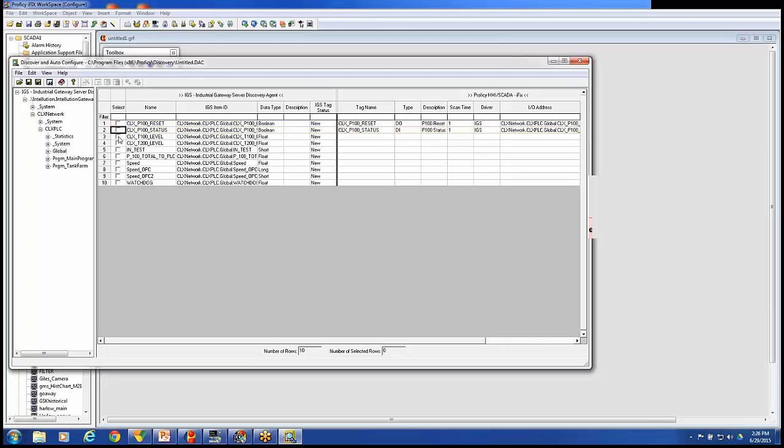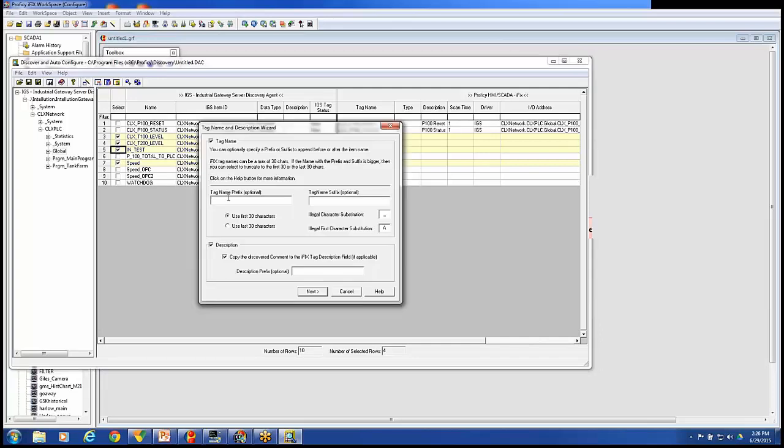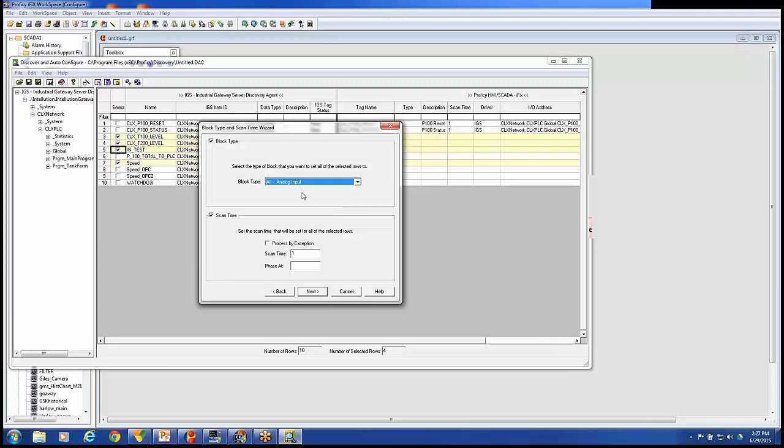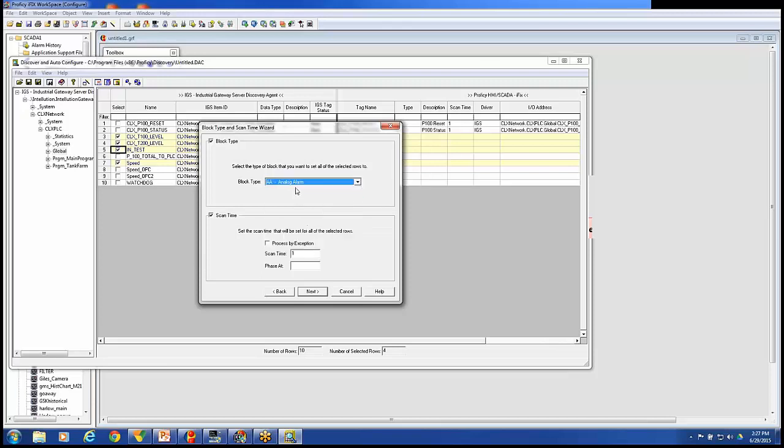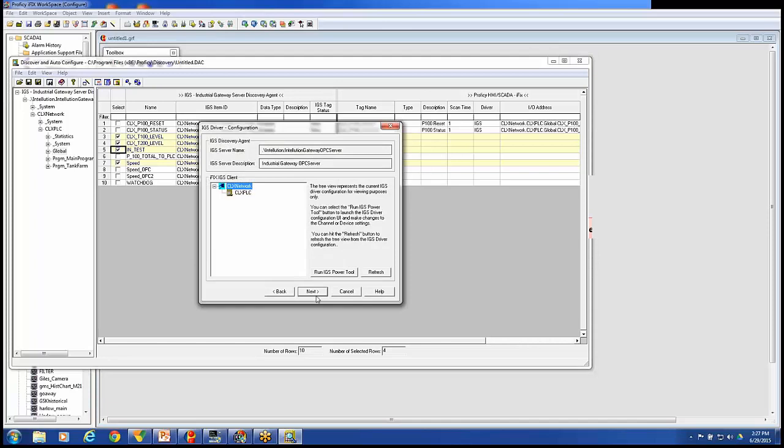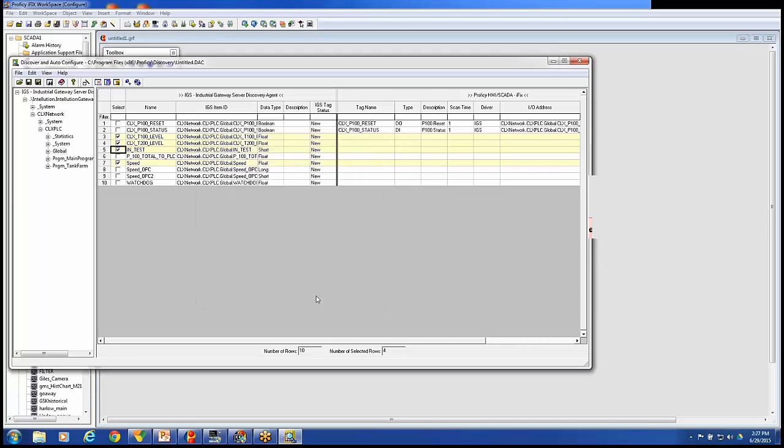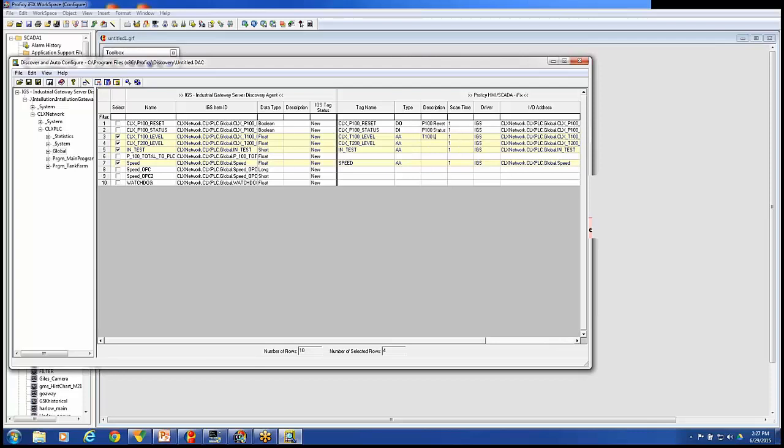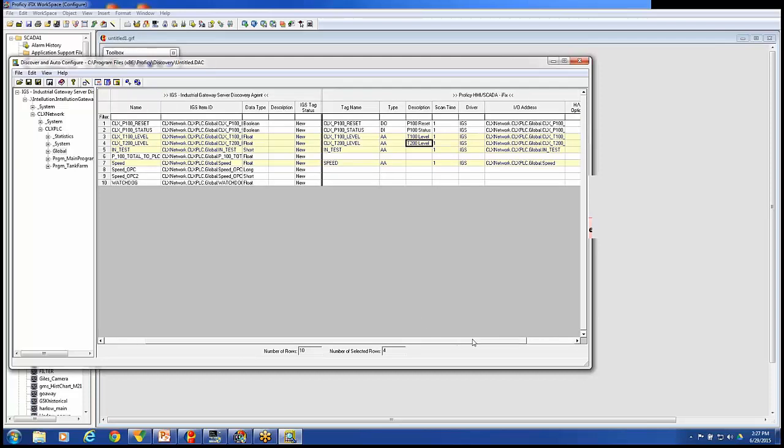I also may want to move over some analog tags. So we'll choose CLX 100, 200, and speed. We'll do IN test also. So I've got four tags here that I'm bringing in. Four more tags. We'll use the wizard one more time. Again, I can put a prefix in front of them, suffix after them, replace illegal characters with underscores, give them a prefix description. Next. We'll choose analog alarm here. So these are analog tags coming in. Default them to one second. Using the IGS driver. The PLC we're connecting to. And finally Finish. So create analog alarm tags. Again, descriptions might be nice things to add while you're sitting in here. T100 level. T200 level.